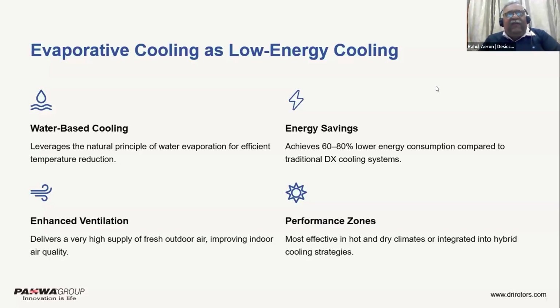The energy savings are huge. You don't have any compressor in this machine, so you can save almost 60 to 80% energy compared to your DX cooling systems or chilled water based systems. And then you have performance zones. Obviously, these technologies work very well in hot and dry climates, but we can also marry them with a refrigeration based cooling system to design these kinds of systems for hot and humid climates like Mumbai and Chennai.